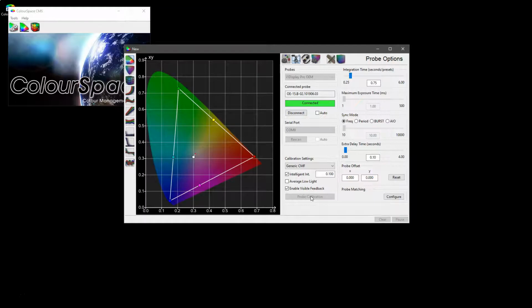If available, the probe calibration will perform either a black or white calibration on the probe itself. On the right hand side we have the probe integration time, which can be set to any given value either using the slider or numerically entering any direct value you choose. Obviously, the longer the integration time, the slower the probe readings will be and the longer the profiling will take.